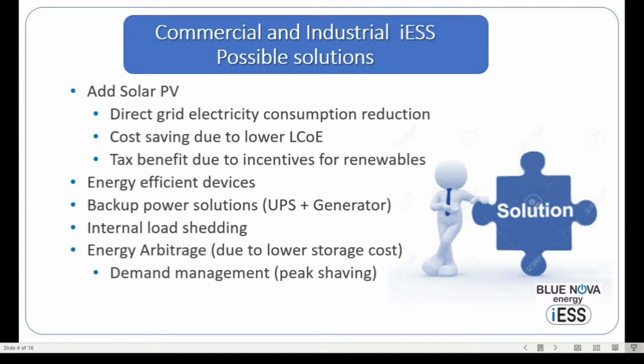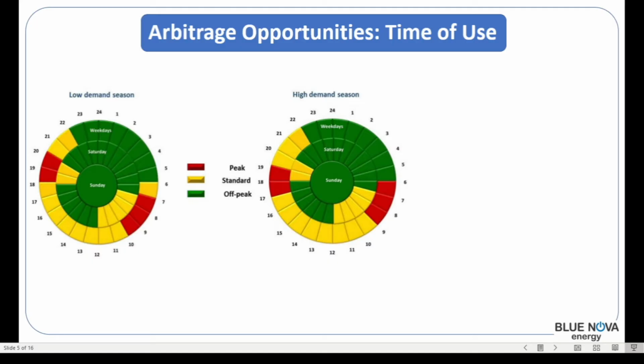So one of the big benefits of the arbitrage or the energy storage is that one can store energy at low cost and then also shave the peaks of your consumption, essentially reducing the peak demand of the plant. And then obviously during the peak periods, one can discharge the storage elements in those slots. I'll show them when those slots are, and also reduce your bill by reducing your spend during the peak periods. One other technique is to adjust the power factor of the plant, and consequently reducing the peak demand of the plant as well. So in principle, the principle of the arbitrage is to, if one looks at these two graphs, we have a low demand season graph, which is typically the summer periods.